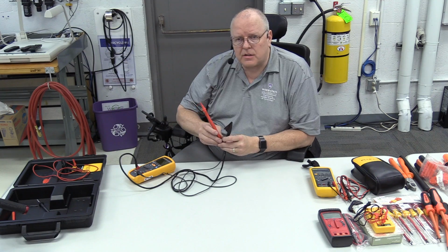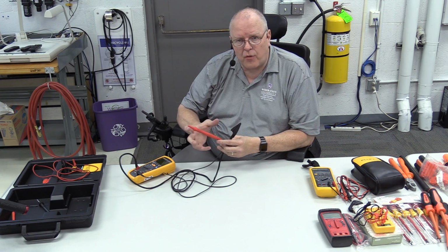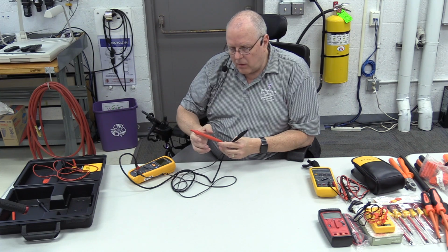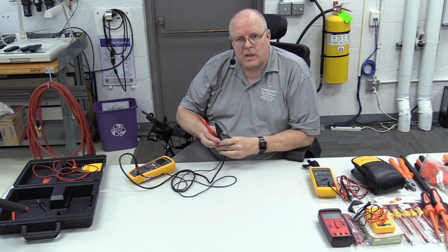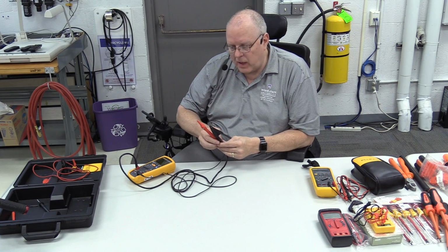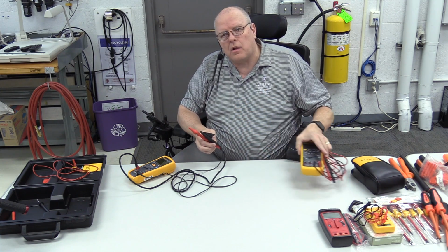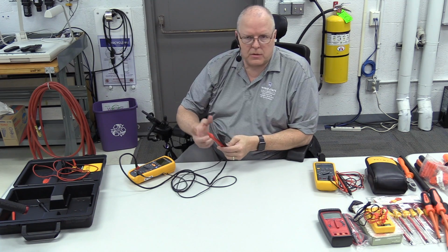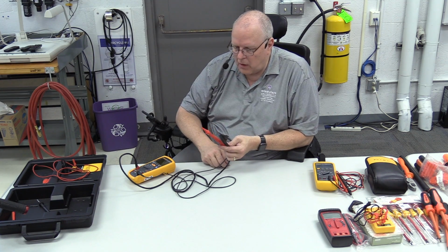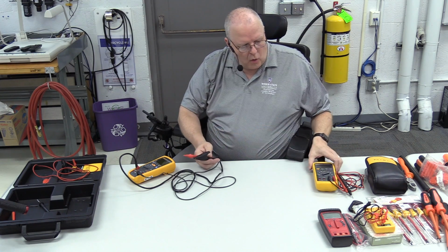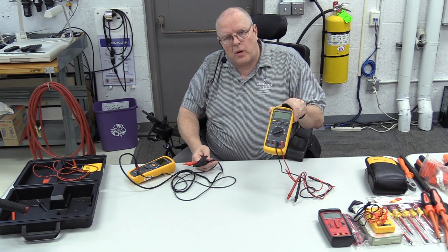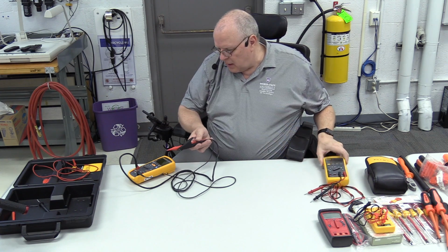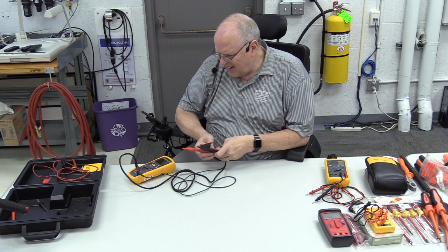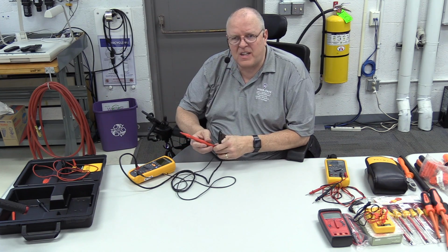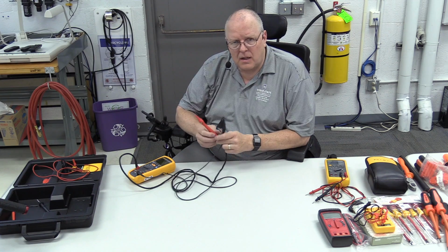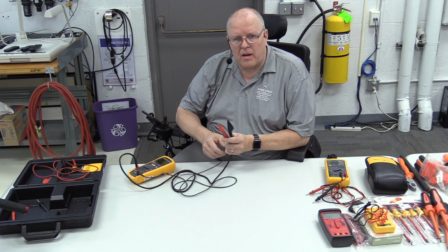So now when we want to check to see if the stator windings are shorted to the stator frame of the motor, we can use this meter. Now normally that would be an open circuit, and so any multimeter would show OL for overload or out of limits, whatever definition you want to use there. But it overloads at 20 megohms, 20 million ohms is all it can measure. This one can go up into, I forget the spec on this one, I think it's 5 gigaohms, 5 billion ohms it can measure with the high voltage there.